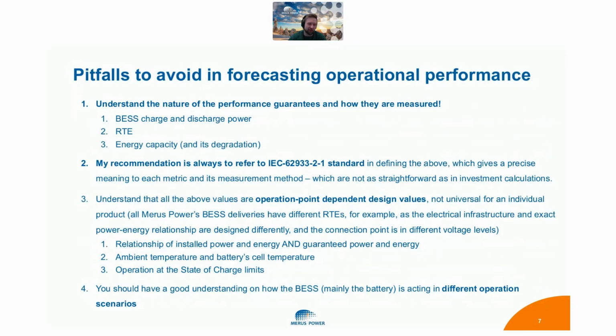The first big realization everybody should have is that all of these, especially round-trip efficiency and energy capacity, are operation-point-dependent design values. They do not necessarily tell you anything about the performance of given equipment. For example, across all the energy storages we have built, the round-trip efficiency is different. This is not due to the products being different at all, but simply due to differences between installed power and energy capacity, system design, and connection point voltage, whether it's medium voltage or 110 kV. All of these affect these values, so comparing, for example, 85% RTE versus 87% RTE tells you nothing if you don't understand the full system design.